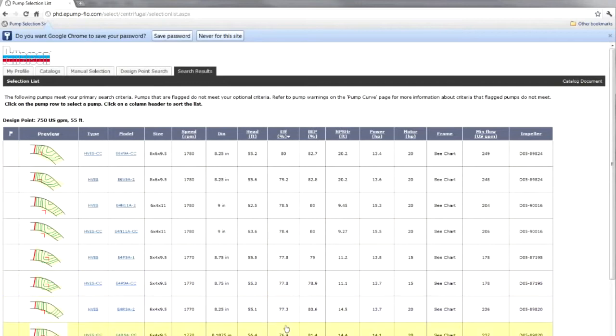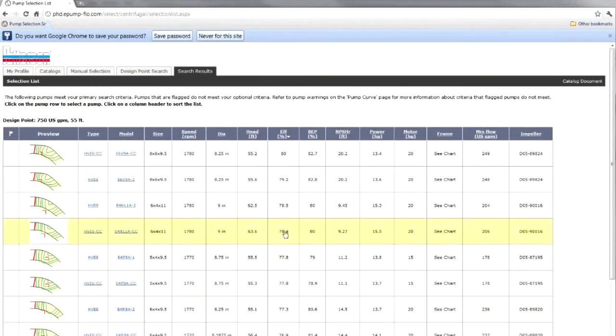We've got quite a few options available to us. Well, if I compare that first pump on the first line to the pump down here on the fifth line, you'll notice the one on the fifth line is operating much closer, probably right at or very close to my best efficiency point.